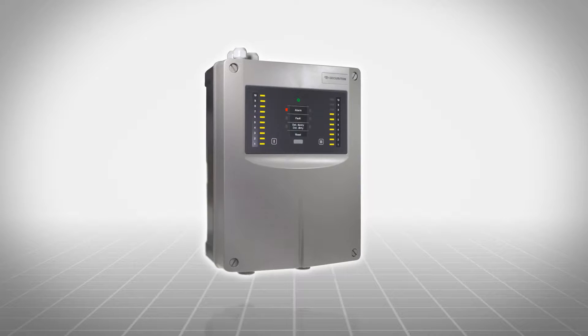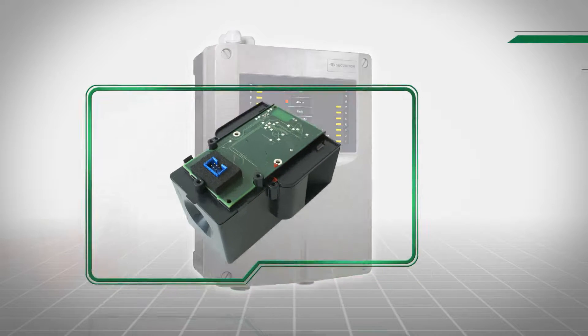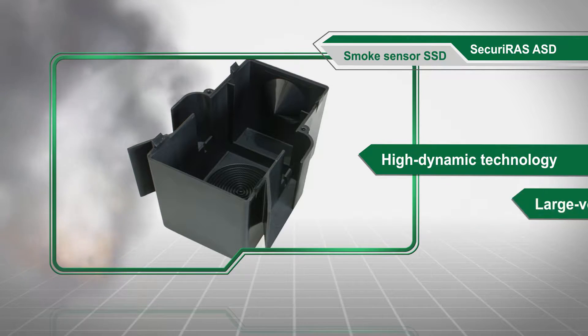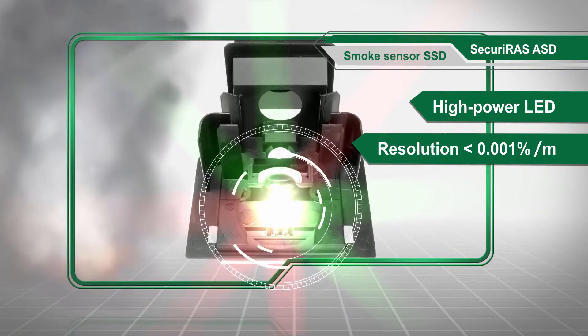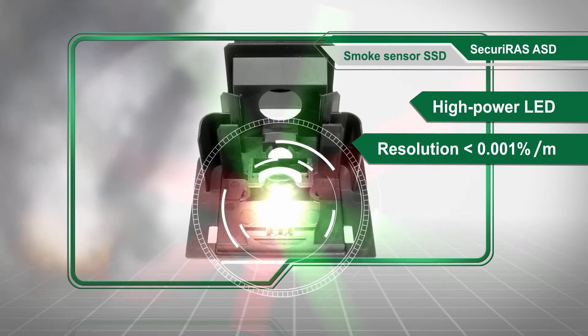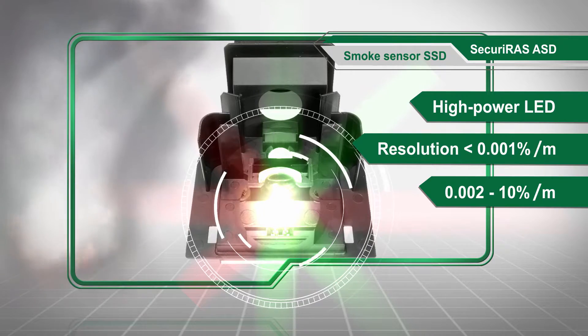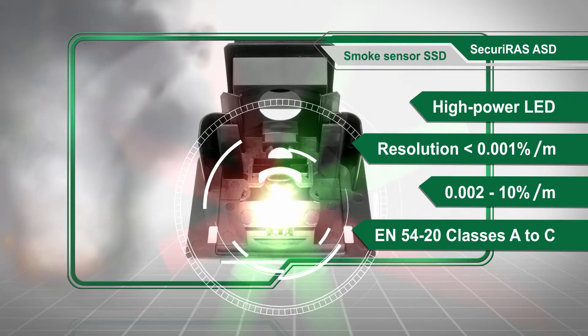At the heart of the SecuriRAS ASD aspirating smoke detector is the highly sensitive SSD smoke sensor with high dynamic technology and large volume smoke chamber. Thanks to a high power LED and a resolution of less than 0.001% per meter, the sensitivity can be adjusted according to the monitoring task — from an extremely sensitive 0.002 to 10% per meter.